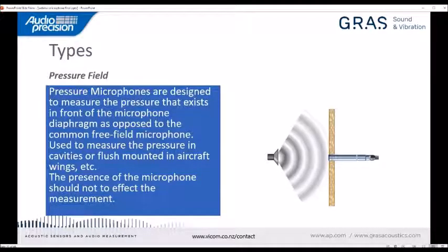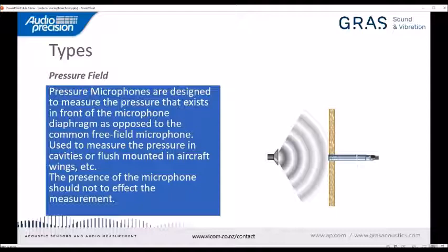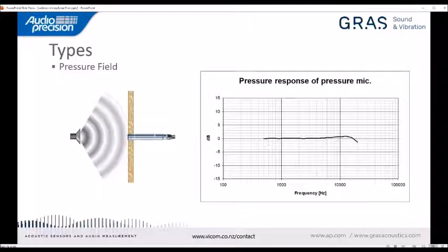A pressure microphone is designed to measure the pressure that exists directly in front of the microphone diaphragm — for example, when mounted flush in a wall, in small cavities, on aircraft wings, or for measuring pressure fluctuations over a surface. A pressure microphone is optimized to have as flat a frequency response as possible when used in a pressure field, and its response is very flat.